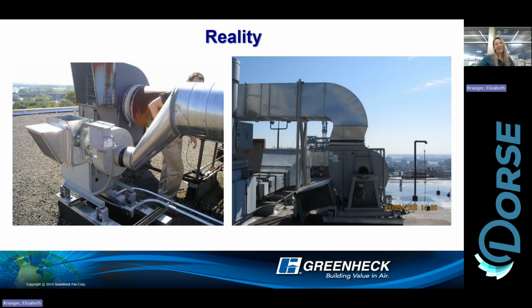So these installs create some crazy system effect. The first picture, as you can see, doesn't have that nice flow into that inlet cone that I'm talking about. Three wheel diameters is normally what you need. Here it's transitioning down into, oh my gosh, a few inches. And it's taking a turn directly in front of the fan. So you're basically cutting off 80% of the airflow there.